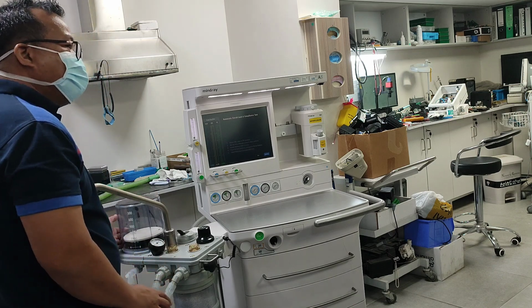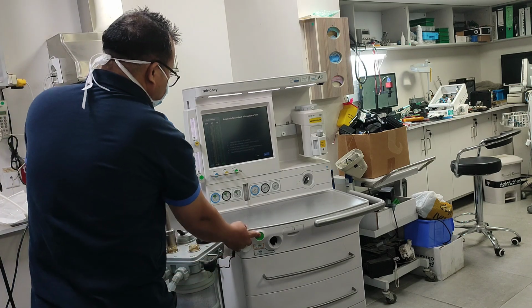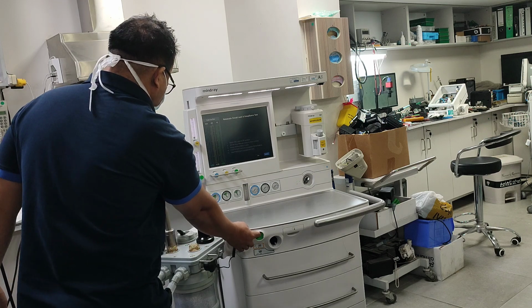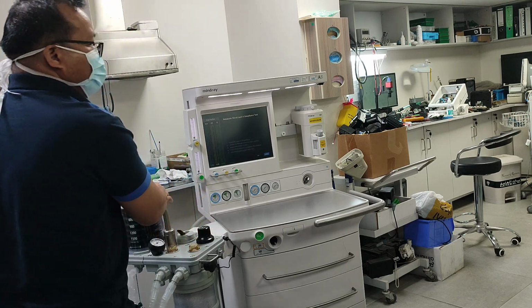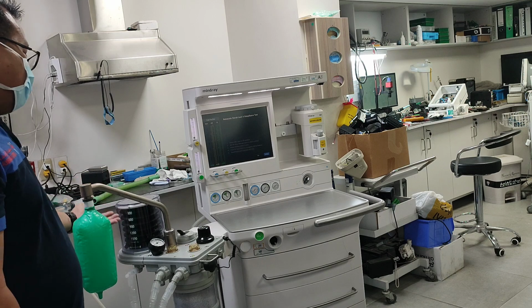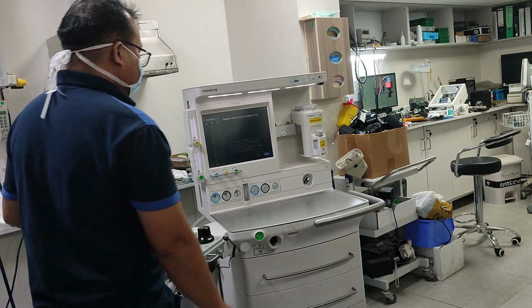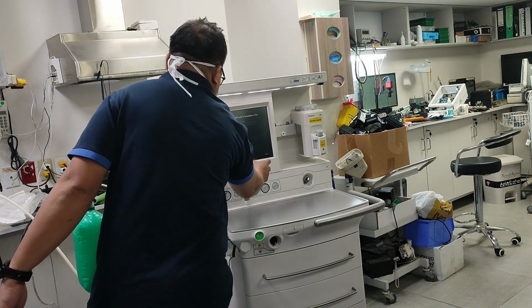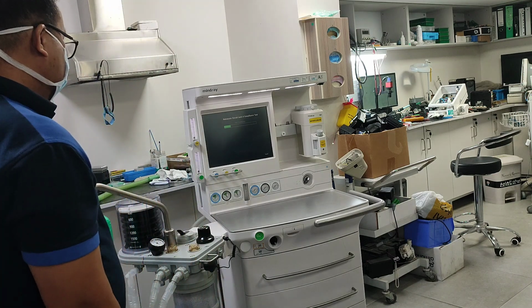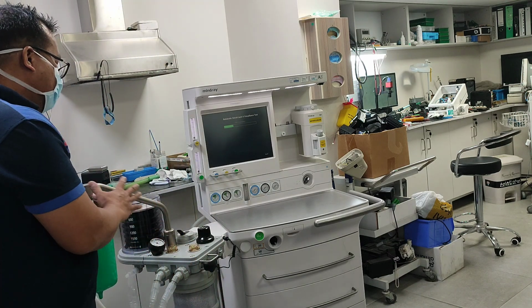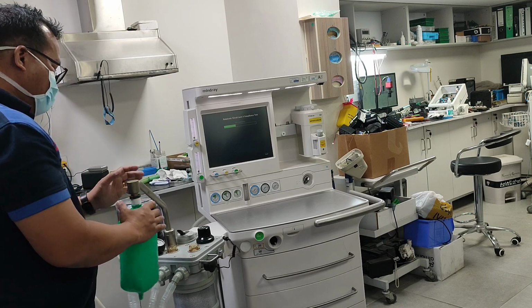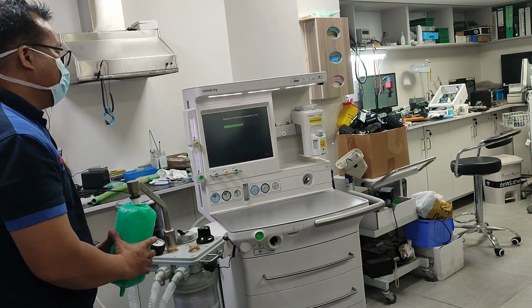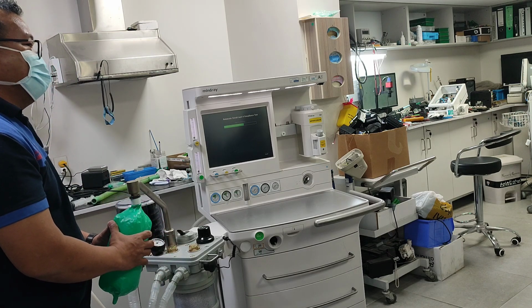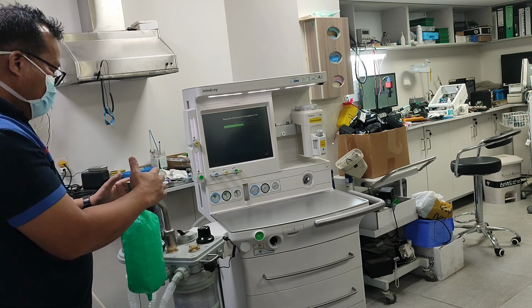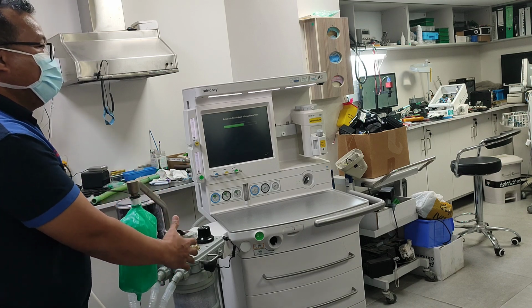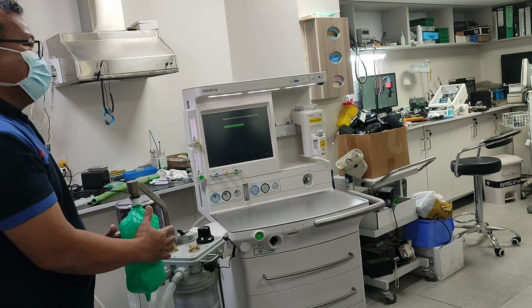There is no pressure here. So we should push the plus button until the bellows are filled. Once the bellows are filled, it's time to select continue. So we are checking the automatic. In the automatic, this one is not included. This one is for the manual ventilation. That's why we checked the manual earlier, to know that there is no leak in the manual while you are doing the manual.